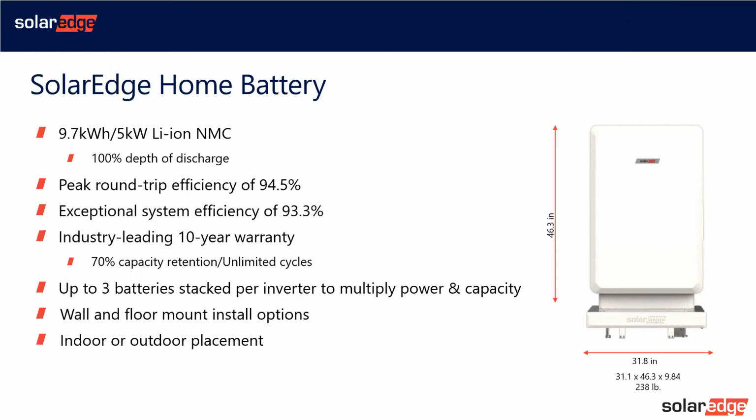Hey, Michelle. Yeah. One thing, when I was at Semper, we sold a lot of Tesla Powerwalls, and what you almost universally would run into on a whole home backup is you'd have to do a panel upgrade. You have to go to 200 amps, and if there were any additional circuits over 30 amps, like air conditioning or maybe a car charger or a hot tub, for an air conditioner you'd have to do an AC soft start or some kind of additional capacity.